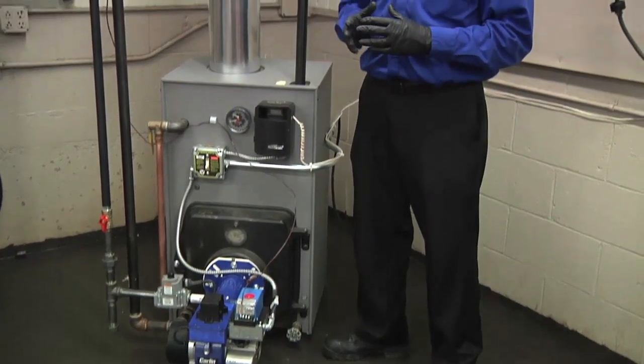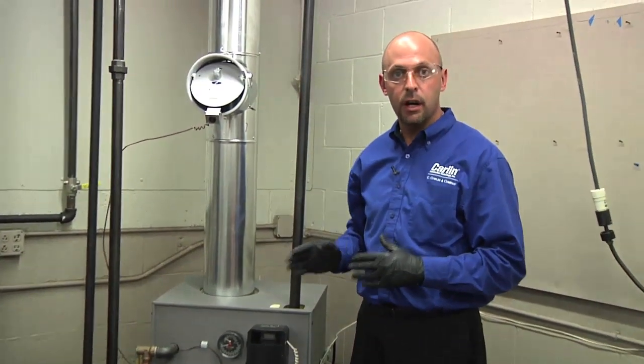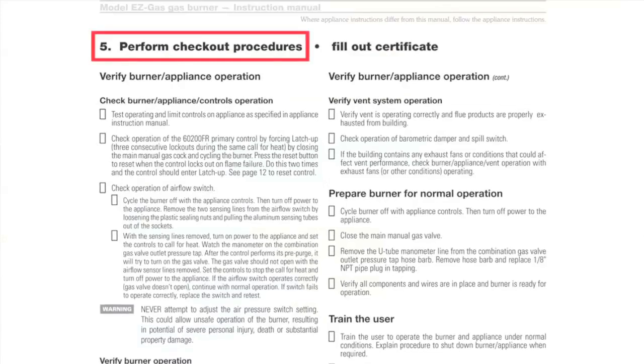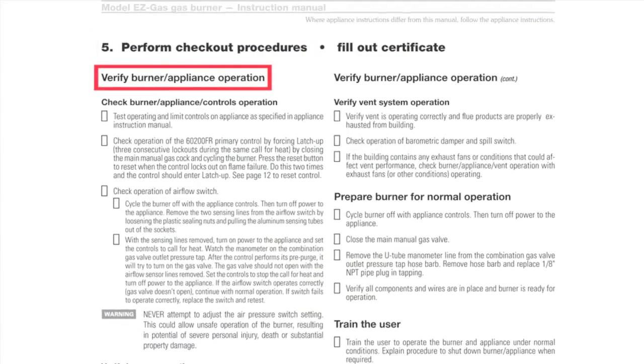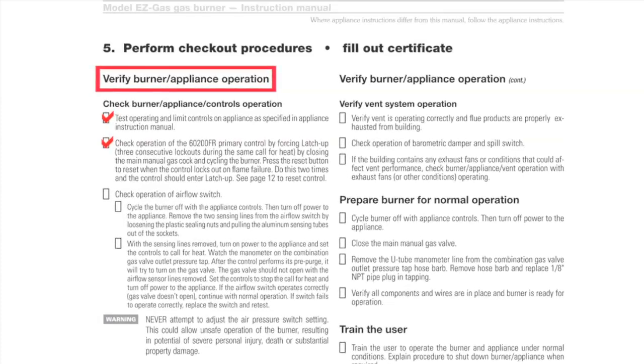Now that your EZ-Gas burner is completely installed, the last thing you're going to want to do is check all your safeties and functions. You're going to want to make sure you turn off your gas supply pressure and the red light comes on the primary control and locks the burner out.